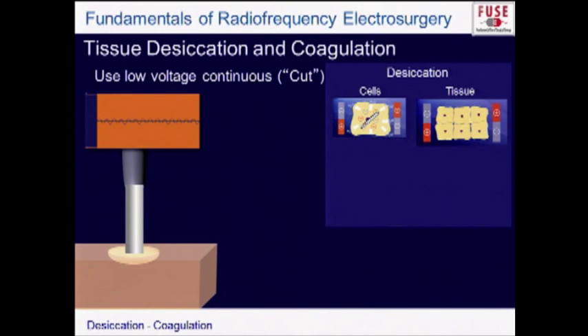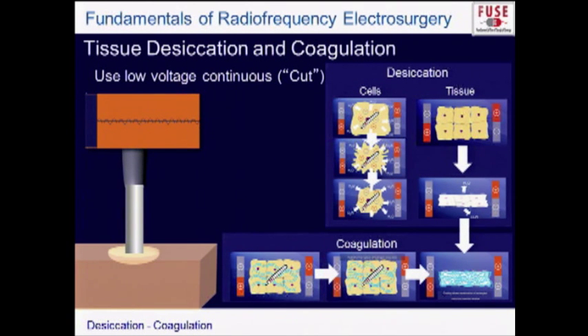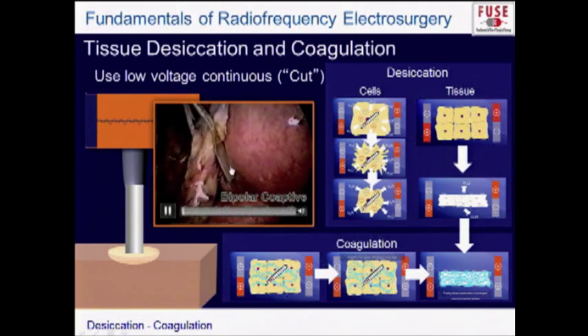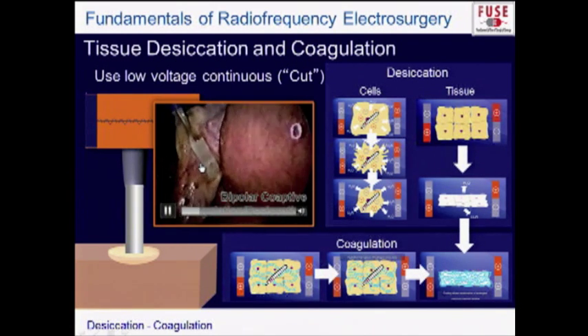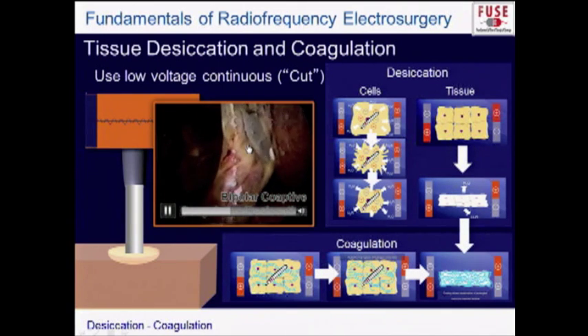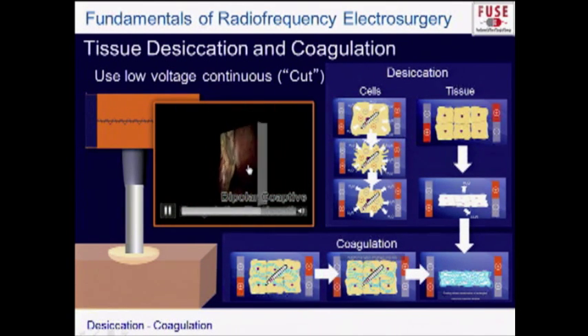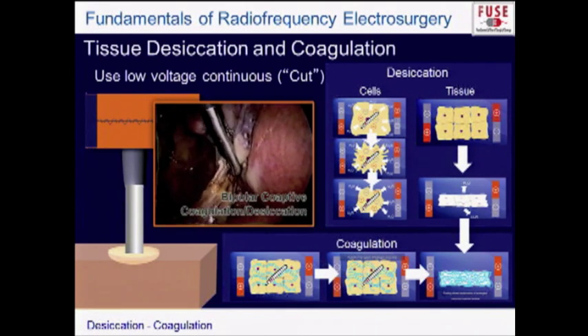Looking at desiccation in detail: cells shrink, tissue shrinks. Coagulation involves the unwinding and rewinding of proteins — we're not destroying the protein as in vaporization; we're maintaining it and using it to create a seal. However, with older paddle-based devices, significant energy escapes around the sides of the ridge, causing thermal spread to areas where you don't want it.